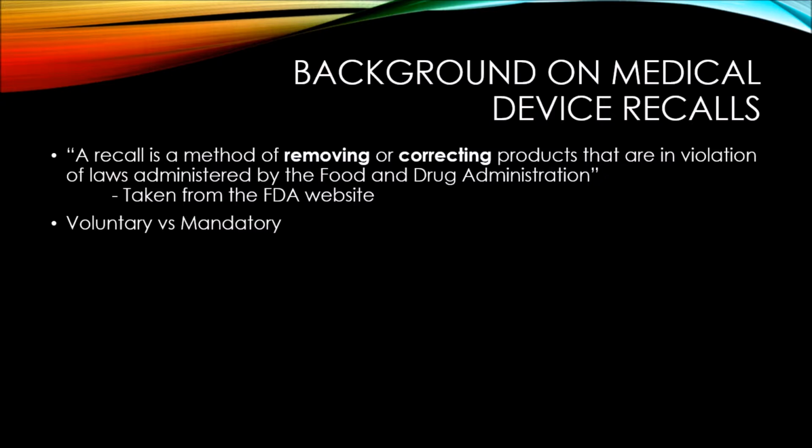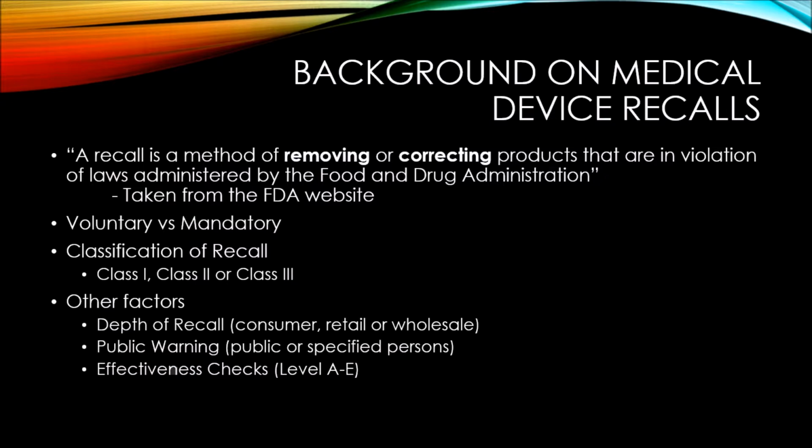And similar to medical devices, recalls also have classes to them. There's class 1, 2, and 3. Contrary though, the classes are kind of reversed. So a class 1 medical device recall, it is kind of the riskiest. It's for the high risk or high harm to the patient. So for example, if a pacemaker wasn't really sending the electrical signals properly, then that would be a class 1 recall because that could mean fatality for the patient. And then class 2 is kind of medium risk, and class 3 is really no risk or harm to the patient.